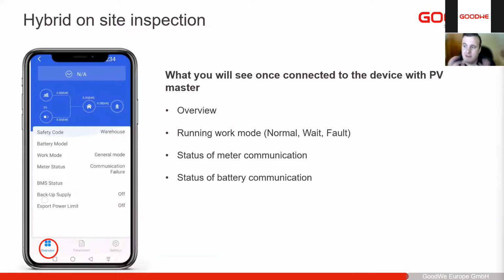So next we go on site. It could be you experience a problem and you're on site already or you're nearby the site. So now we head straight to site to go and see exactly what's happening with the customer. You'll open PV Master, connect to the device, and from PV Master we'll get all the information you need. On the front page, you'll see the running work mode, the status of the meter communication, and the battery communication. So also the running work mode: normal, wait, or fault.